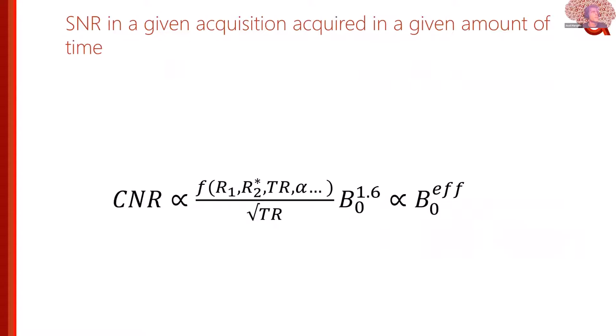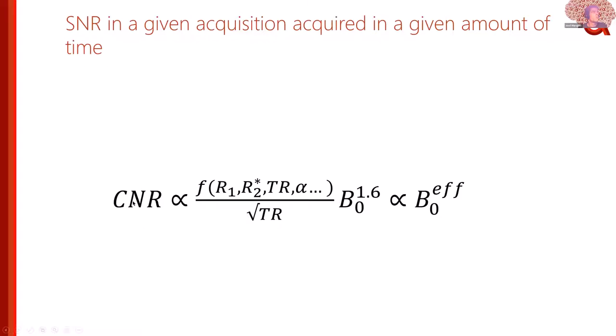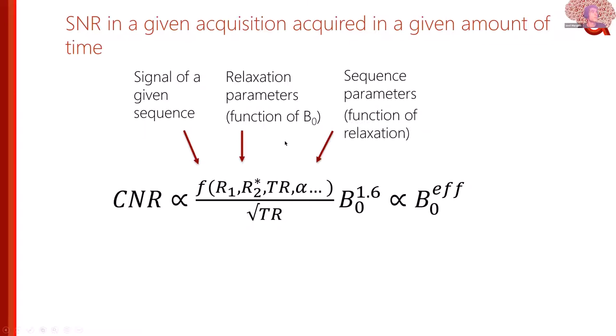There is extra complexity here: what we care about is not just SNR but how much contrast we have between different structures, and how much contrast we have in a given amount of time. To frame it properly: you choose a pulse sequence, consider its relaxation parameters as a function of field strength, optimize the parameters based on relaxation, and then maximize acquisition efficiency.